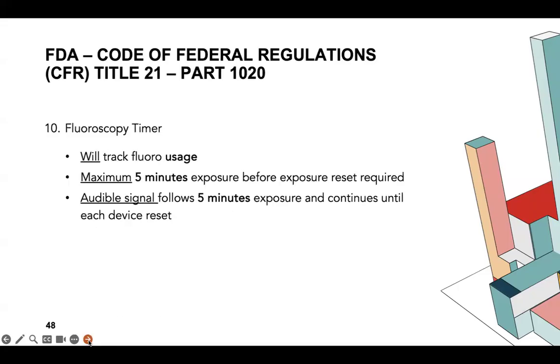Then lastly, it tells us about our fluoro timer, that we have to have a fluoro timer, number one. This allows us to track the fluoro usage, that you get a maximum of 5 minutes exposure before a reset is required. And then you have to have an alarm or audible signal that lets you know when that 5 minutes exposure has occurred, and allows you to basically reset the device.